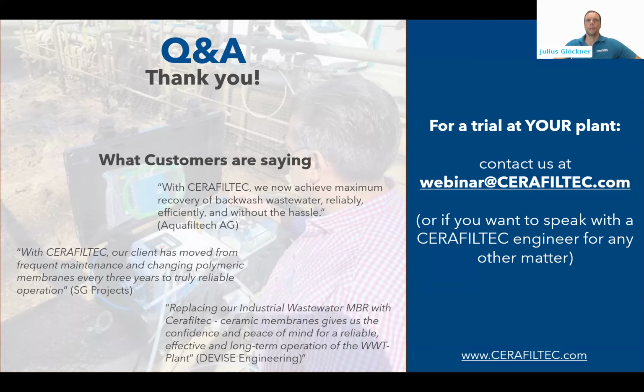Yeah, I also think all of that stuff essentially goes into wastewater. It doesn't go to the front of the plant to contaminate further feed water. It goes to sludge processing. Yeah, the return water actually has no chlorine at all. After the cleaning, it's flushed and rinsed, typically followed by an acid cleaning, and then there is almost nothing in the filtrate. It all goes to the wastewater, and that's why typically there is also an additional wastewater treatment, or the water goes to the wastewater treatment plant.